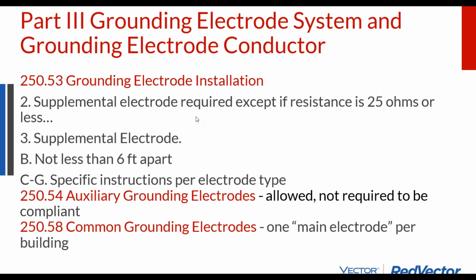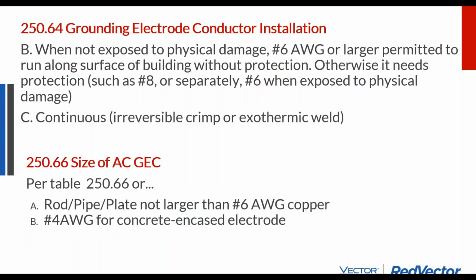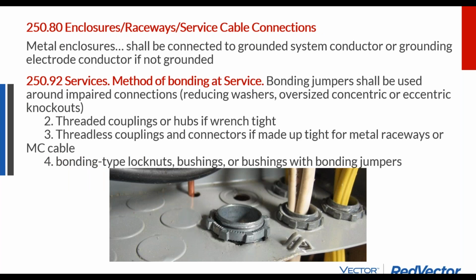You can buy a testing device to test your resistance to ground. In dry soils and in rocky soils, putting in an additional ground rod is not a bad idea. The ground rods have to be spaced 6 feet apart to function. And now we're coming up towards the end of the program, and we haven't made it into section 300 yet. So just some common gotchas, and then we'll end.